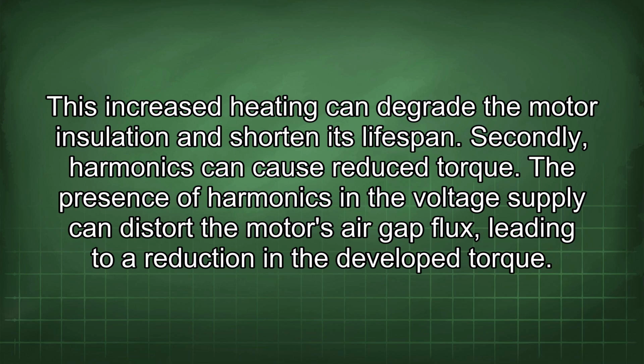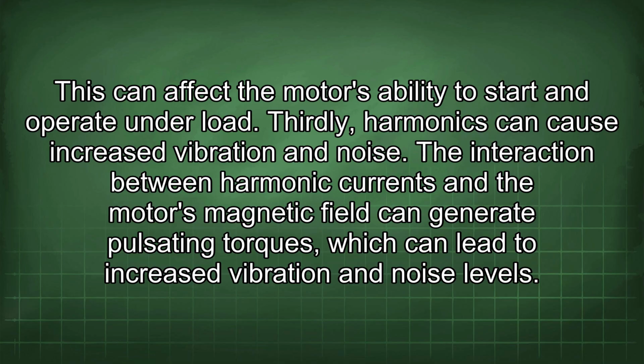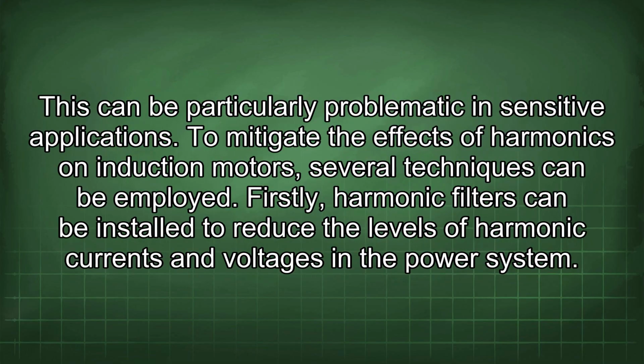Secondly, harmonics can cause reduced torque. The presence of harmonics in the voltage supply can distort the motor's air gap flux, leading to a reduction in the developed torque. This can affect the motor's ability to start and operate under load. Thirdly, harmonics can cause increased vibration and noise. The interaction between harmonic currents and the motor's magnetic field can generate pulsating torques, which can lead to increased vibration and noise levels. This can be particularly problematic in sensitive applications.